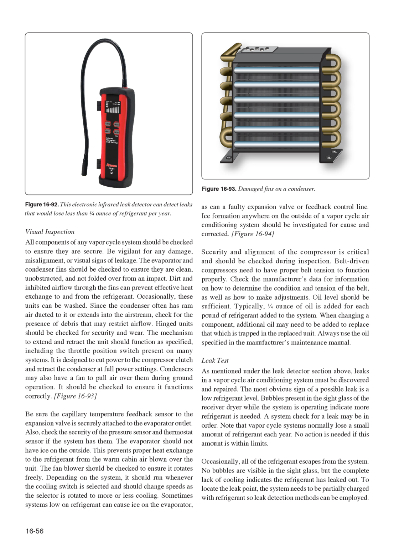Note that vapor cycle systems normally lose a small amount of refrigerant each year. No action is needed if this amount is within limits. Occasionally, all of the refrigerant escapes from the system. No bubbles are visible in the sight glass, but the complete lack of cooling indicates the refrigerant has leaked out.